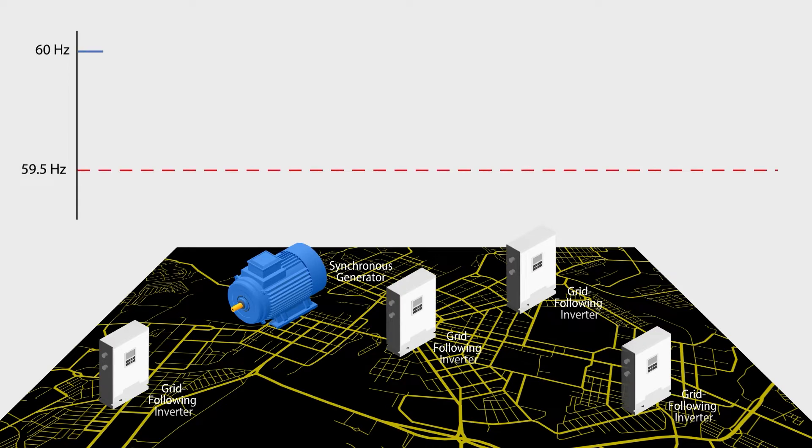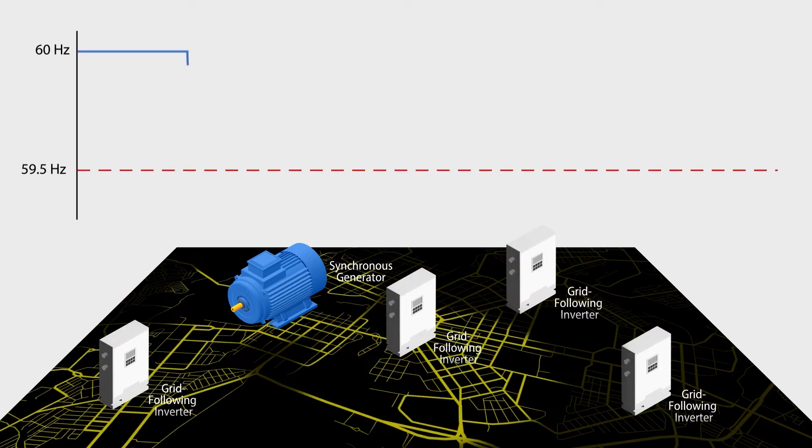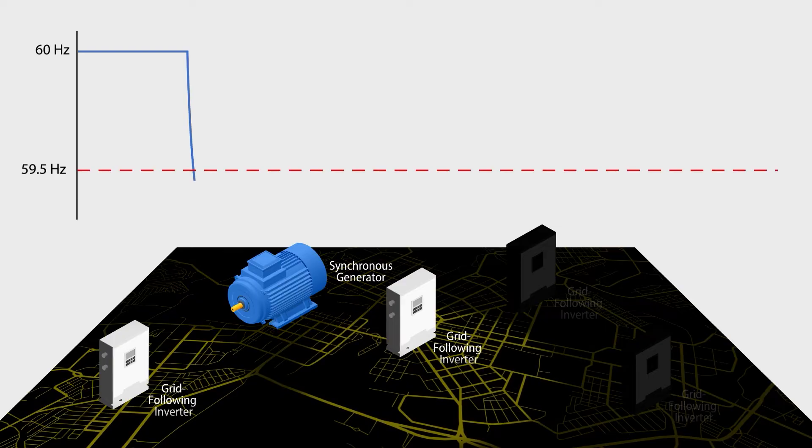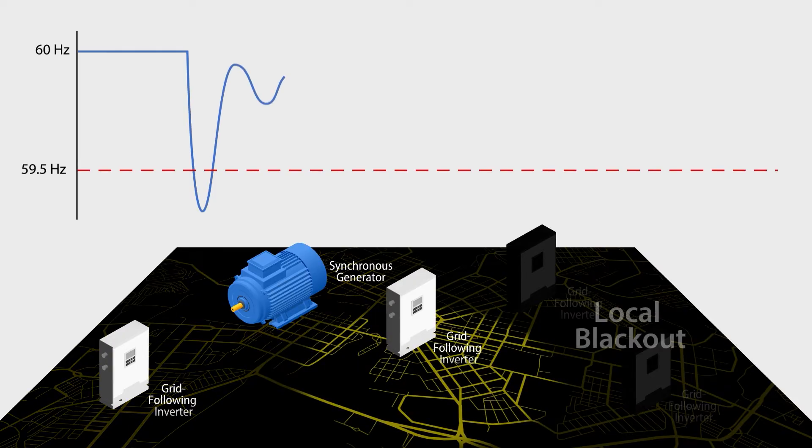Imagine that an inverter trips during a storm. This causes the frequency to drop quickly, while the remaining generators and inverters try to stabilize the grid. As the frequency drops below 59.5 Hz, the grid automatically begins an emergency recovery scheme.